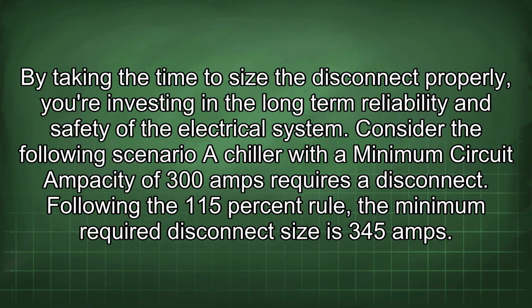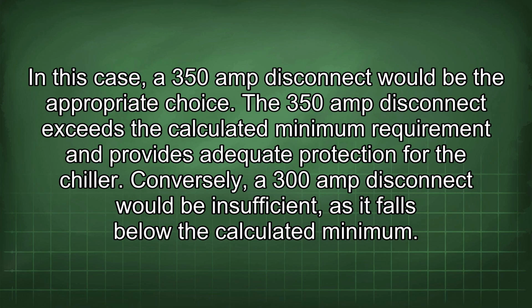Following the 115% rule, the minimum required disconnect size is 345 amps. In this case, a 350 amp disconnect would be the appropriate choice. The 350 amp disconnect exceeds the calculated minimum requirement and provides adequate protection for the chiller. Conversely, a 300 amp disconnect would be insufficient as it falls below the calculated minimum.